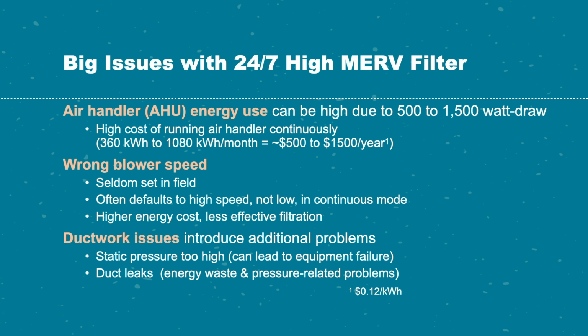But it's all about whether or not the amount of air you're trying to move through the duct system is appropriate for that duct system. Basically, in most of the cases we see, the static is too high, which can lead to equipment failure. Now, a clogged filter can also lead to too high a static pressure. It can be undersized ductwork, it can be an oversized HVAC system. But anyway, this whole issue of whether or not the air handler system is properly sized for the furnace or AC unit is a really big one.